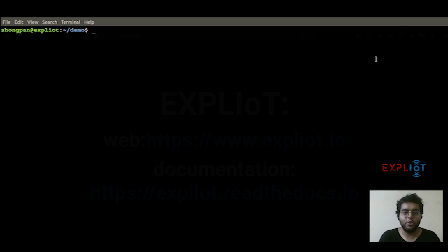So now for the demonstration, I'll be using an open source tool called Modbus PAL. Modbus PAL is basically a Modbus simulator. It can simulate from one to multiple slaves at the same time. For our demonstration, I'll be simulating only one slave. Other than that, I'll be showing this demonstration for Modbus TCP, which is basically a Modbus implementation over a TCP/IP network, and it uses port number 502 for the communication.